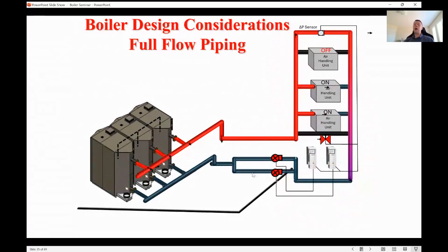As I said, this type of high mass design allows for much more variation in flow rates. They generally have a much lower flow rate they can operate at, and a much higher one they can go to. For example, a lot of them are between 10 and 110 GPM, in the residential, like commercial sizes. Some of the big commercial ones go between like 30 and 350 or even 550 GPM, and they handle variations in flow quite well. So you can go to that same situation where we have VFDs on the system. You can just eliminate that primary loop and have it pumping directly through something like this. That's another way that you can deal with that situation where you might get less flow in the system loop than the boiler loop. But there's other ways as well.